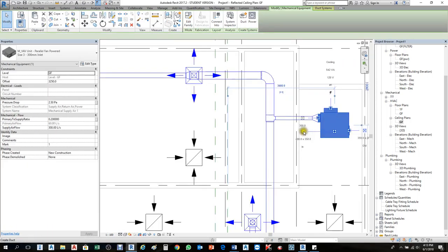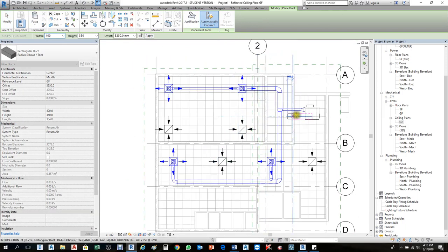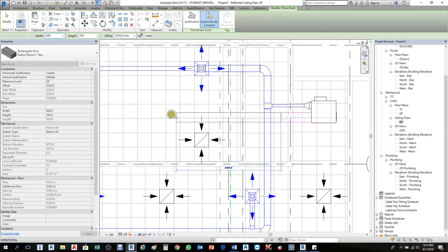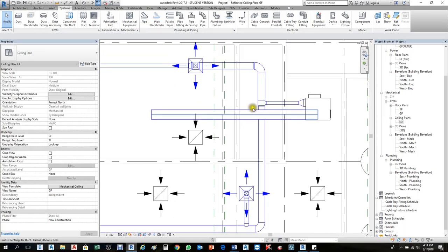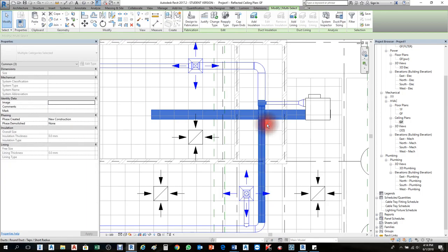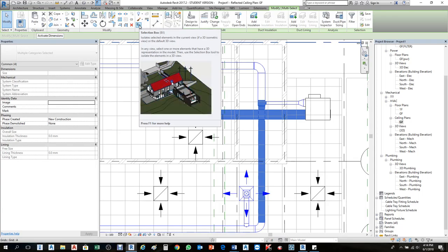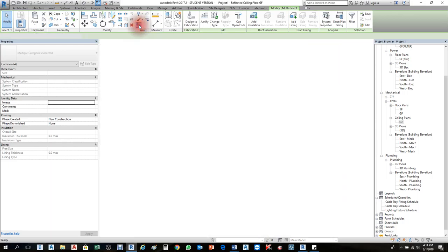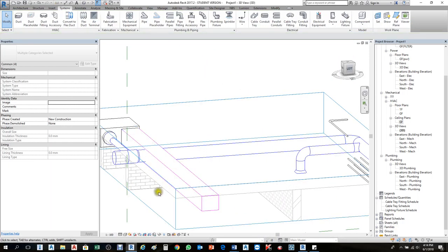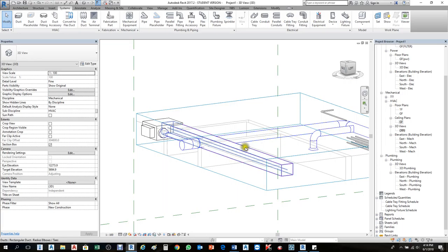Again, from here, we will have return. I'll make it one up. So if I go straight ahead, it will clash with this. First, let me go straight. And let's check if we have a clash between these two. I'll select these two, Control, and go to 3D. We don't have this option in Revit 2015, this 3D. But if you install software 2016 and above, you can easily check it in 3D. So I'll go ahead, take a look. See now, this pink color is clashing, the return system is clashing with the other one. So I need to make it up.